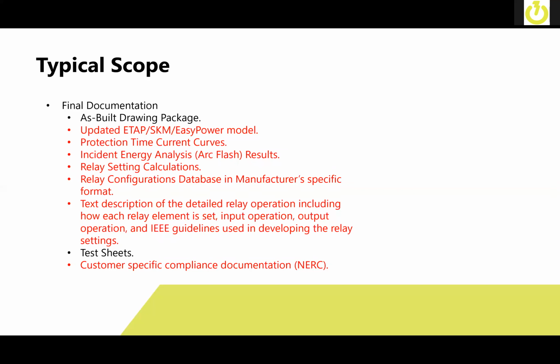Along with a text description of the detailed relay operation, including how each relay element is set, the input operations, the output operations, and the IEEE guidelines used to develop the relay settings. Test sheets showing full test results for all the testing performed during the installation phase. And also customer-specific compliance documentation such as NERC for generating facilities or transmission facilities where these retrofits are performed.